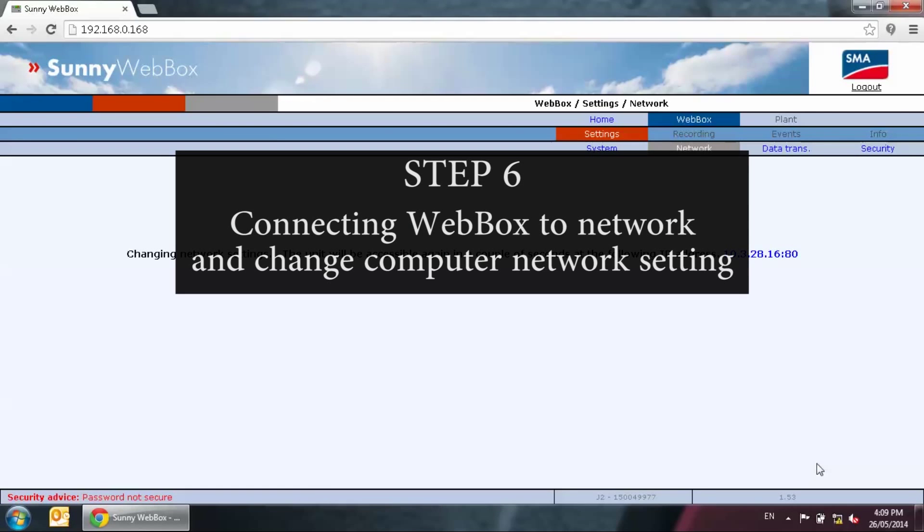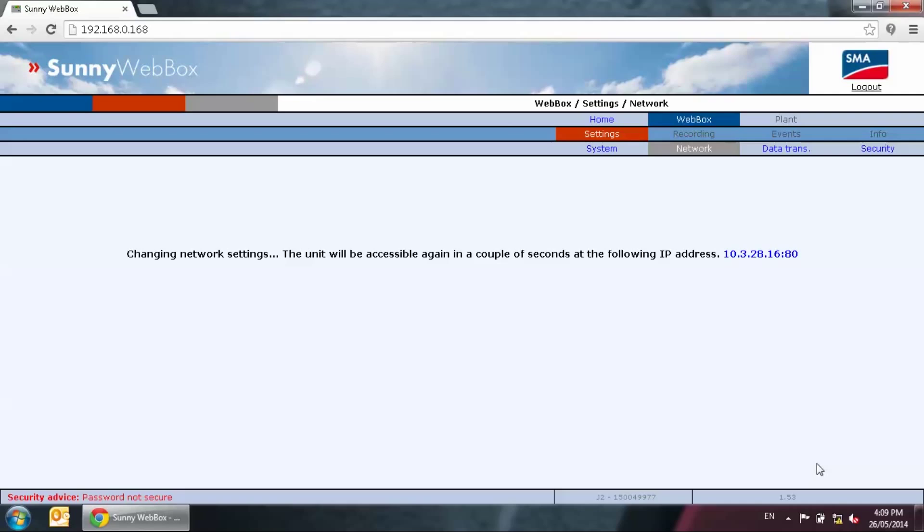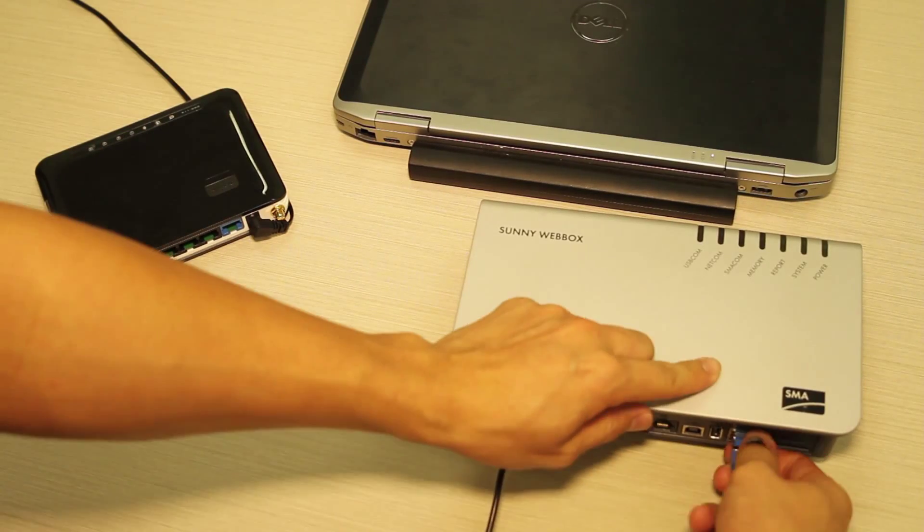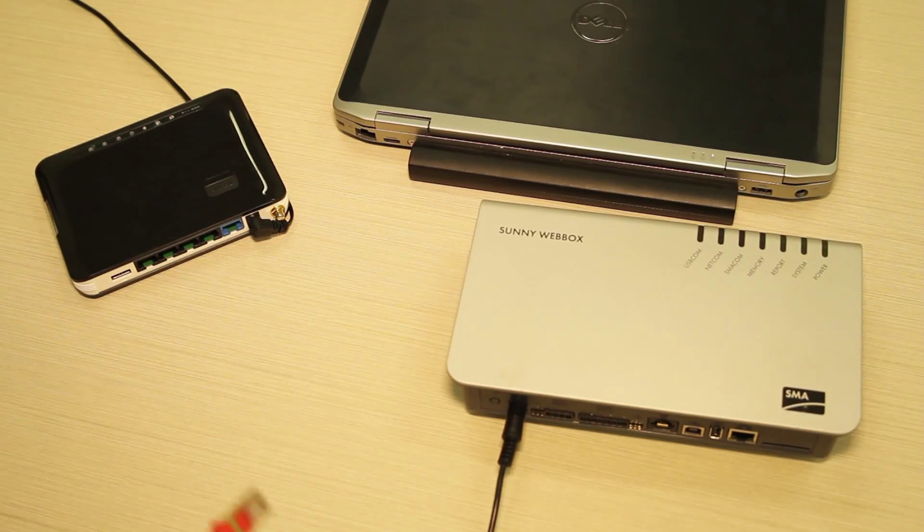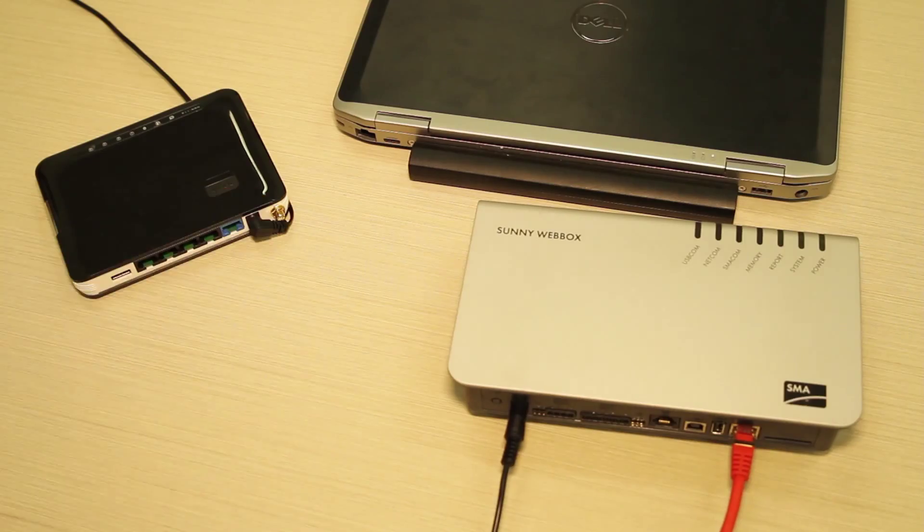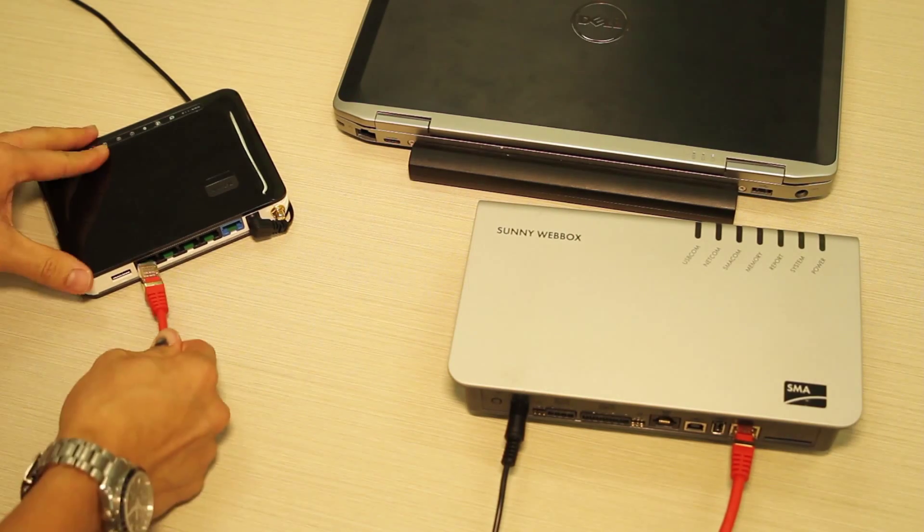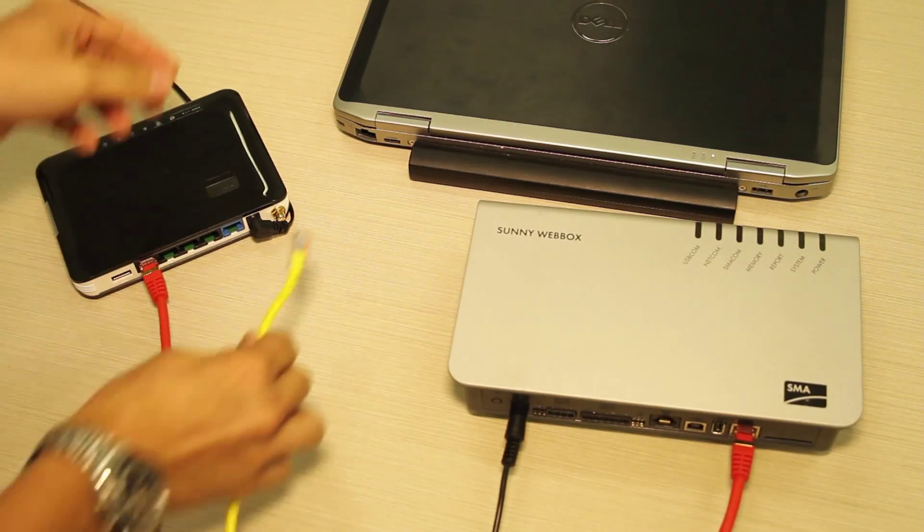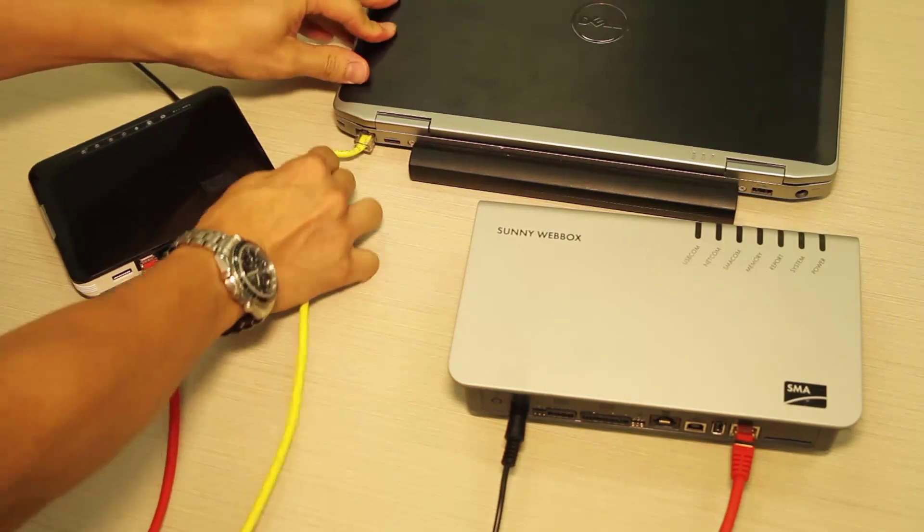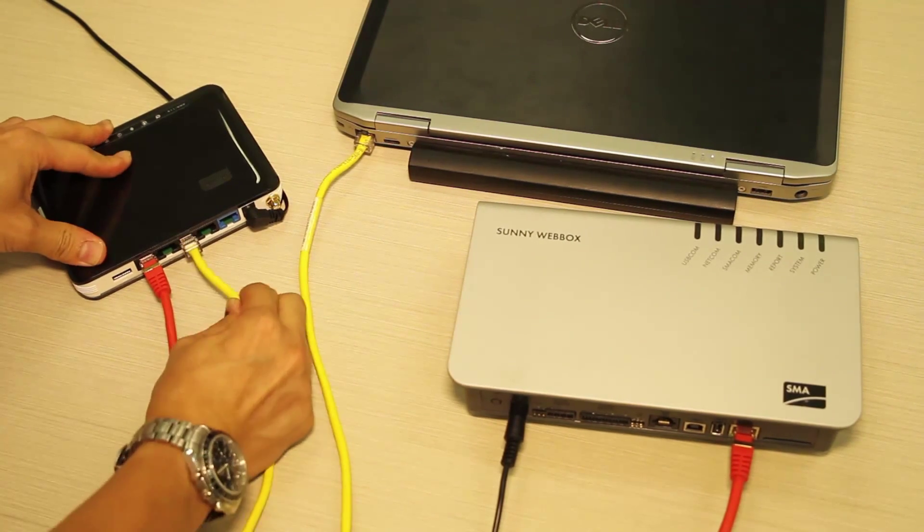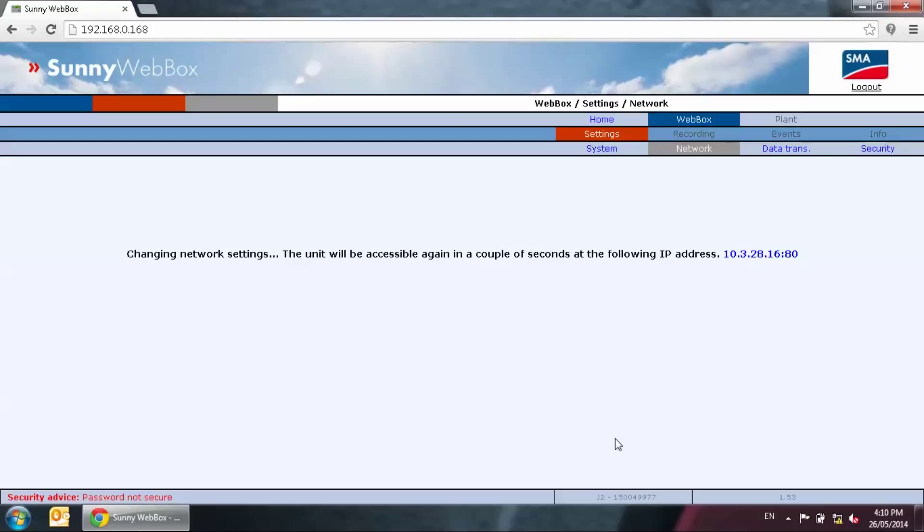Step six, connecting web box to network and change computer network setting. The screen will say that the web box is now changed to the new IP address. You can now unplug the blue crossover cable and connect the web box to the local network with the red patch cable that's delivered. Also, connect your laptop to the local network with an extra patch cable that you've got. Remember in step two that we have changed the laptop setting to 192.168.0.100. We need to change it back to auto detect so the server can allocate an IP address to the laptop.